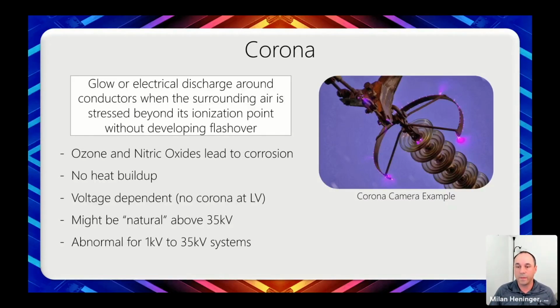All right, so if I go into my medium voltage gear and I hear corona, that's going to start a set of actions to be able to inspect and figure out where it's coming from and be able to mitigate it, because the nitric oxide will cause kind of this white powder on your terminations and cables. That's actually the corrosion and the material getting eaten away from the nitric oxides. So we want to prevent and eliminate the sources of corona, which can often be sharp little points and things like that that are in there.